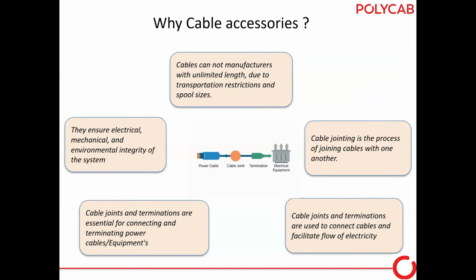So as our topic says, the importance of cable accessories. Why important? Here I have mentioned why cable accessories are required. Cable accessories are required because, first, we have to join the cables. We cannot manufacture cables kilometer after kilometer; they come in 500 meters or 1000 meters. We cannot manufacture 2, 3, or 10 kilometers because of two reasons: transportation restrictions and spool sizes. That's why cables are always manufactured in 500 meter or 1000 meter lengths. Then cable jointing is the process of joining two cables with one another, or terminating at one end.